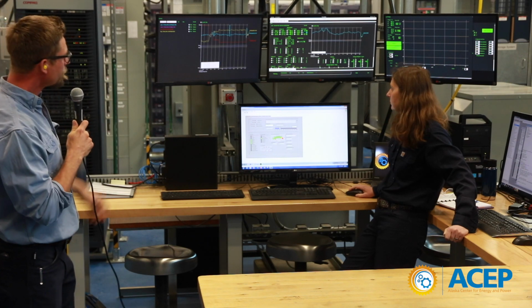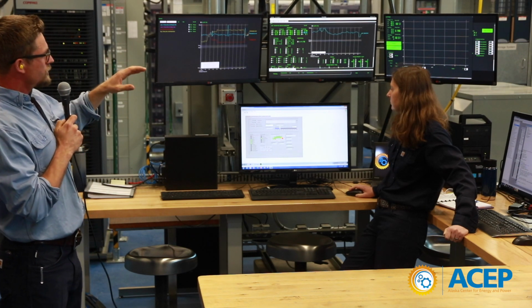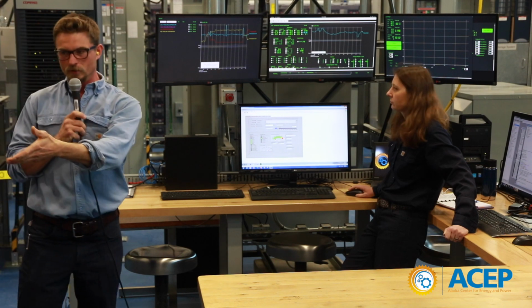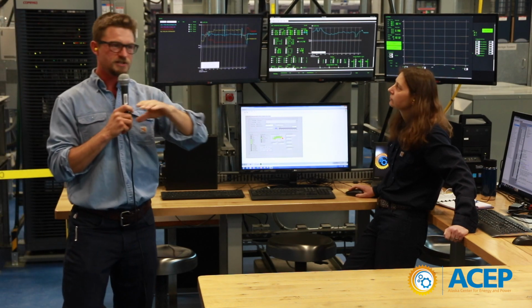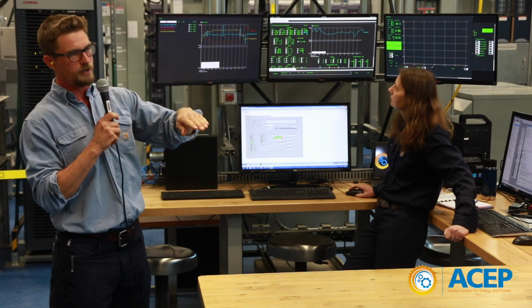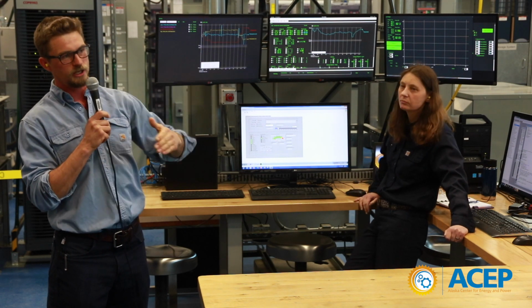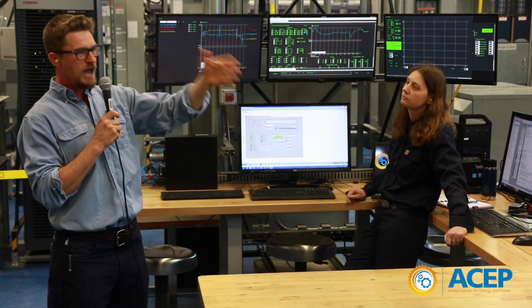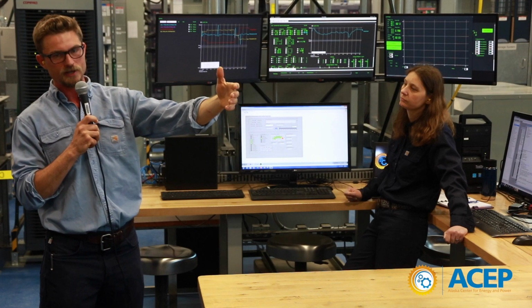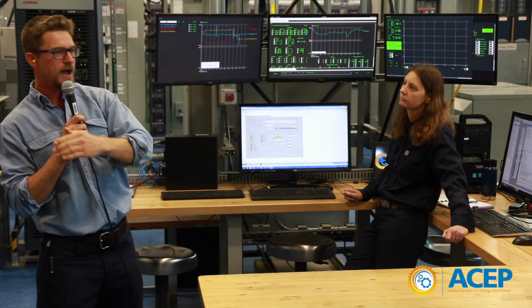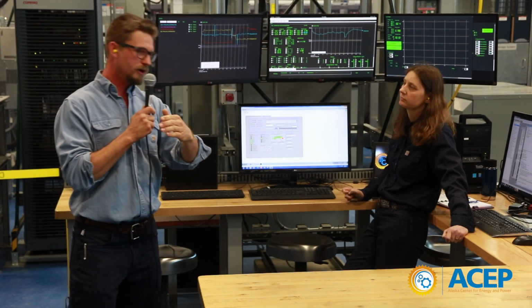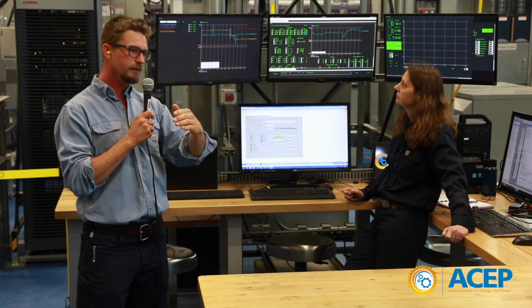So we need to manage this, and that's where minimum loading comes in as well. Usually let's say we want to keep 30% loading on our generator. That means we need to curtail our wind power. If we're able to produce 50 kilowatts of wind, we have to rein it back so that we're only producing 30 kilowatts of wind power.